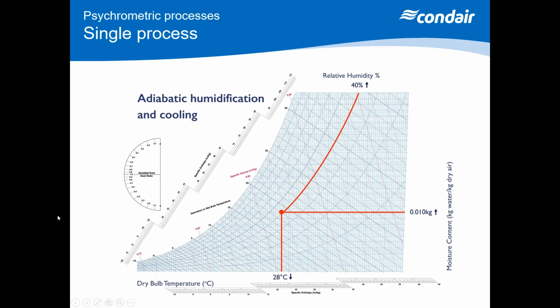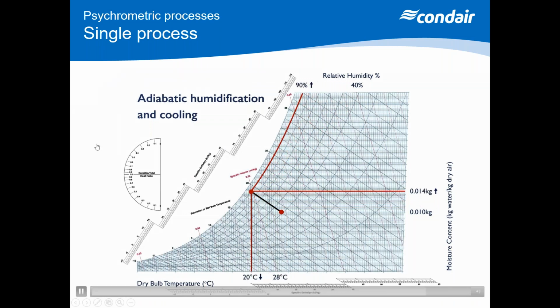Finally is adiabatic humidification and cooling. Now here I'm doing one of two things. I'm either passing the air through a wetted media that's porous and evaporating the water off that material, or I'm spraying water in a very small aerosol, a droplet-sized aerosol, into the air and letting it evaporate. And when I do that, I follow the line of enthalpy. So the line that we drew from this scale, intersecting our condition, to the bottom scale, and again, the angle of that line will be dependent on the value of the top scale and the bottom scale being the same. And that gives us this line that we draw as our line of process.